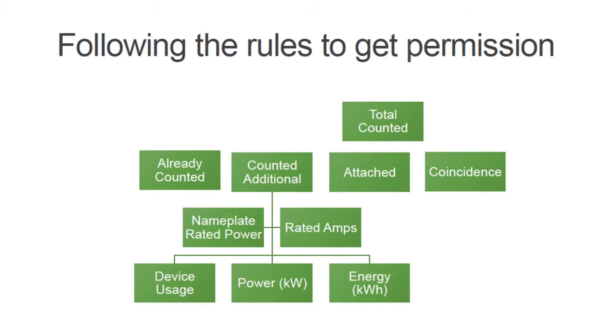So that's an example of interesting things about what 'attached' means, and when it applies, and then what coincidence is. We basically total up the already counted additionals, multiplied by their proper coincidences, and we get the total counted watts. We convert it to amps, check it against the panel rating, and that's how we get permission to operate with that panel, or whether we have to move up to the next size panel.